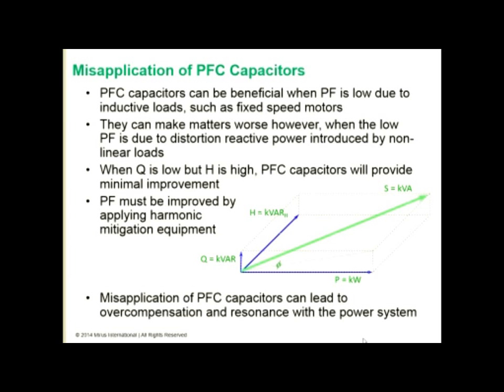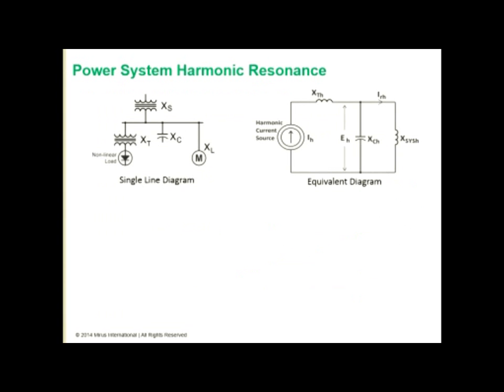So in this three-dimensional diagram here, we show a very small component of inductive reactive power, but a much larger component of distortion reactive power, and the vector sum results in a high level of kVA. Misapplication of power factor correction capacitors can lead to overcompensation and resonance with the power system, because applying power factor correction capacitors to improve this power factor will not improve the power factor very much. And what can happen is we can introduce a system harmonic resonance condition.